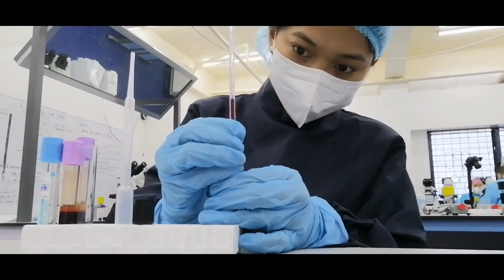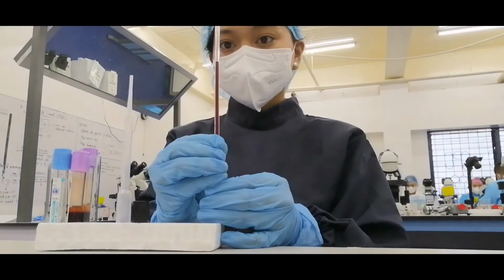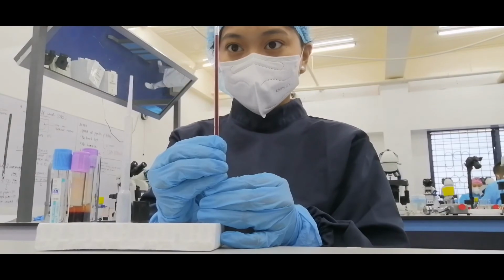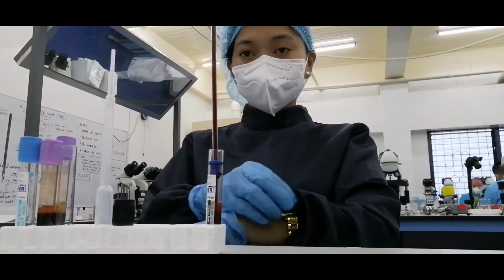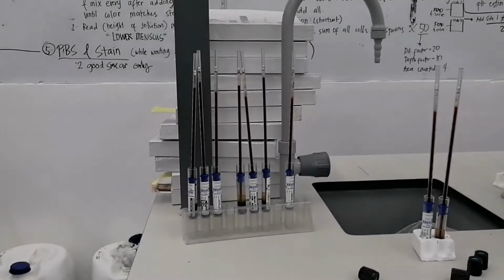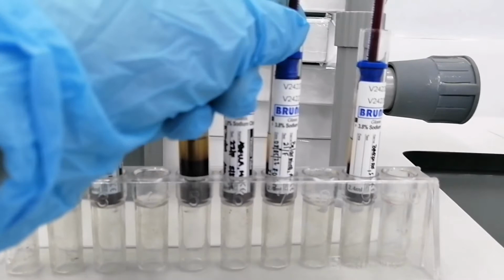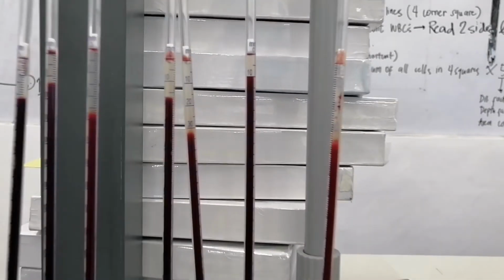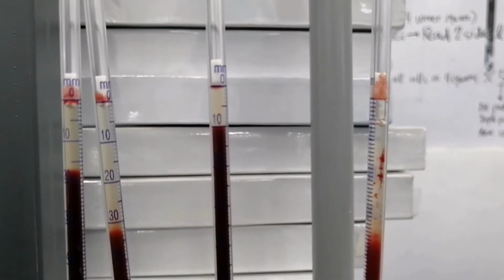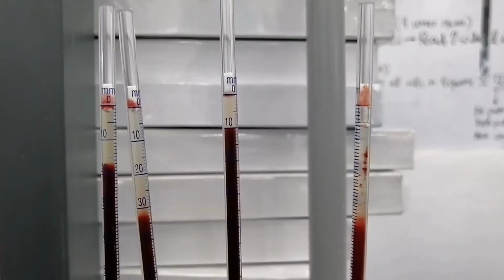Insert the disposable Sediplast pipette gently with a twisting motion while pushing down until the pipette rests at the bottom of the vial. The blood that enters the pipette will be auto-zeroed and excess blood will flow into the seal reservoir compartment. Set a timer for 1 hour and let the pipette stand undisturbed for exactly 1 hour. Using the scale on the side of the tube, read the meniscus where the red cells are packed.